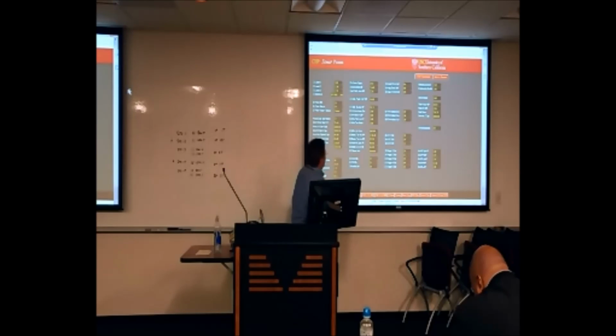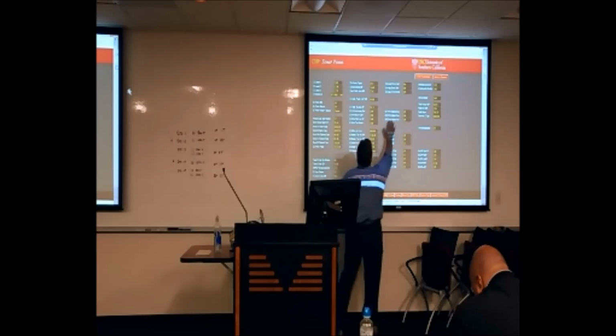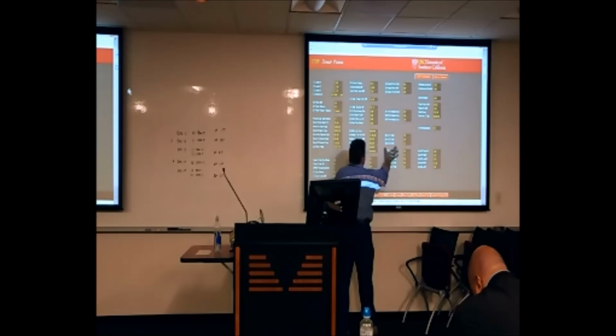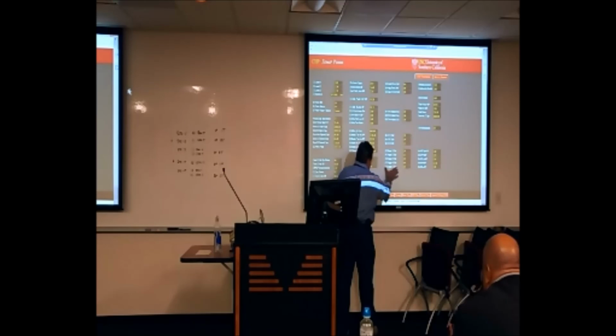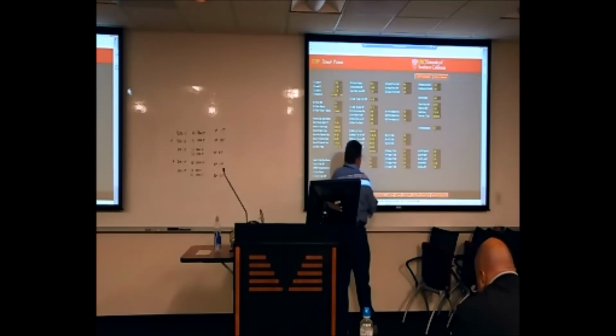There are some related points right here. Here are our tower maintenance switches. For information, there's the lead condenser water pump call, lag condenser water pump call, and lag 2 condenser water pump call. Here are our stage calls over here. These are the stage calls from the central plant for the tower based on the equipment that's running.